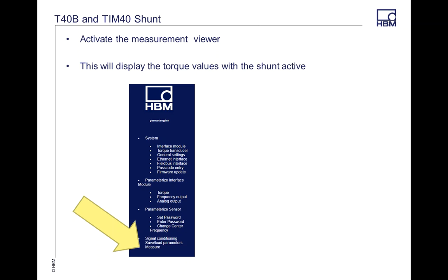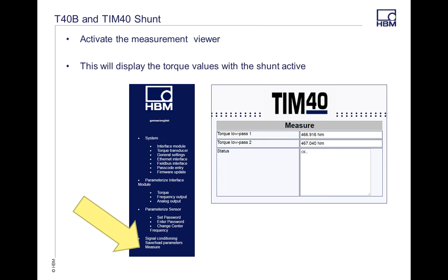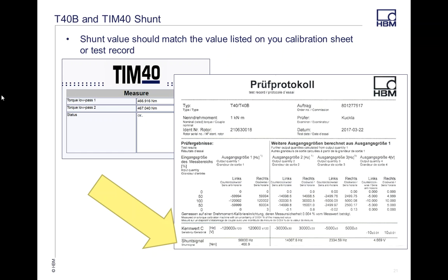On your main screen, go to Measure. That's going to give you another pop-up box, and it's going to show the values on your shunt with your shunt active. This value, for example, is 466.9, and if you pull up your calibration sheet, that value matches, or it should match what's on your calibration sheet. So that's how you can go through a couple of different options to activate a shunt on your torque transducers.